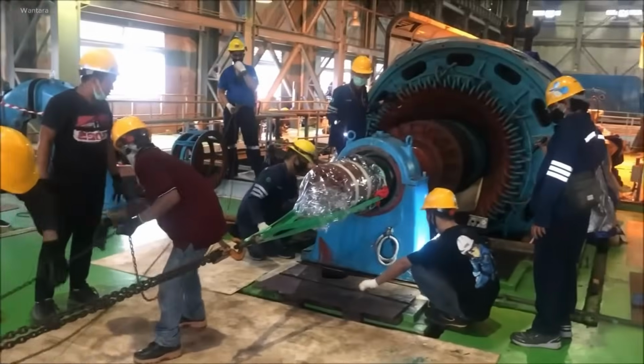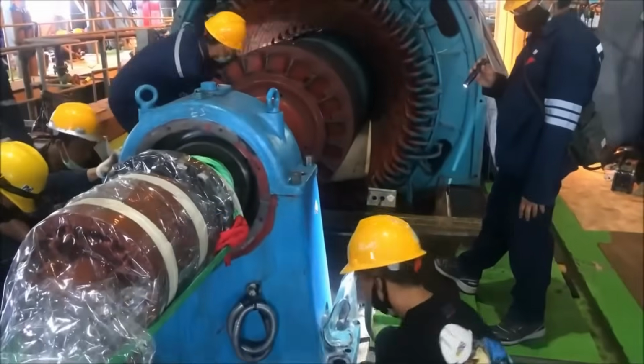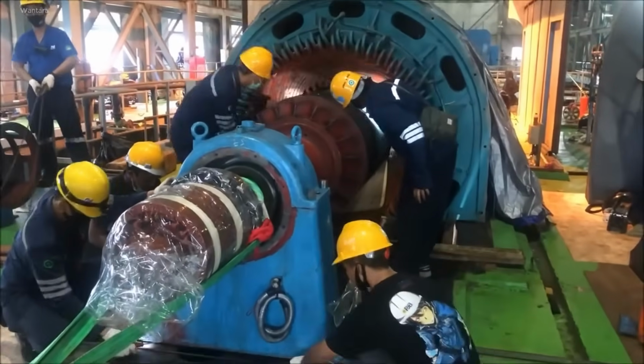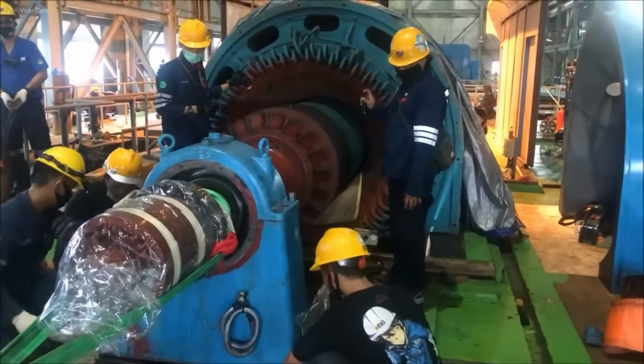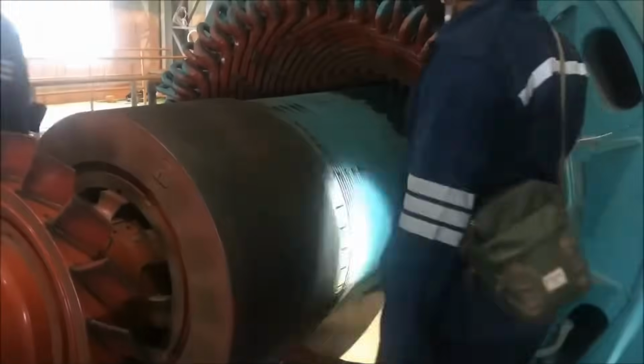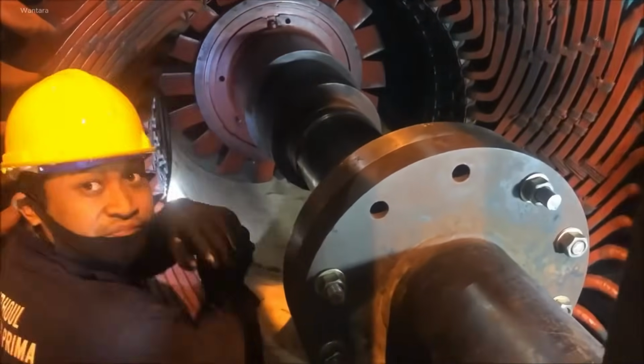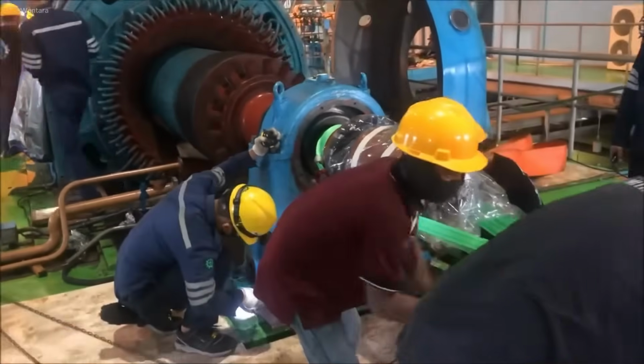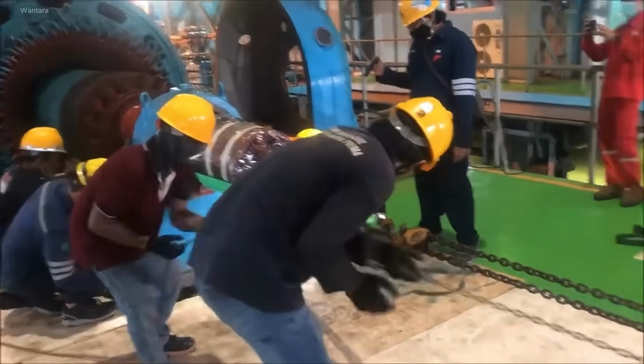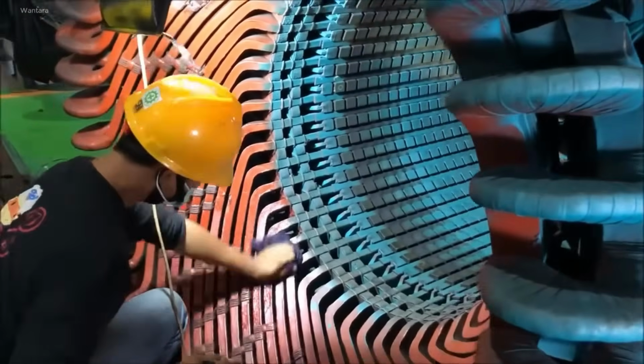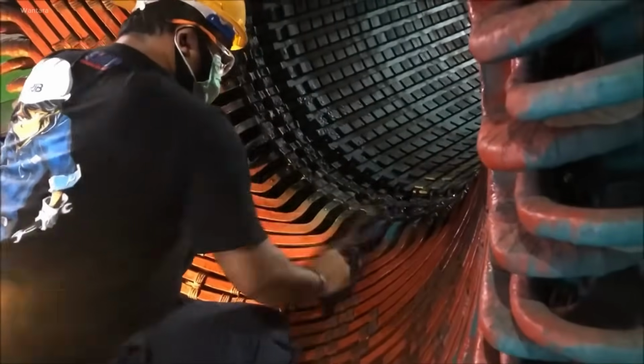The maintenance process of the 16.5 megawatts generator begins with pulling out the rotor. Both the rotor and stator are thoroughly cleaned to remove any dust or contaminants. Bearings are then inspected to ensure proper function. A remaining life assessment is performed to evaluate the condition of critical components.